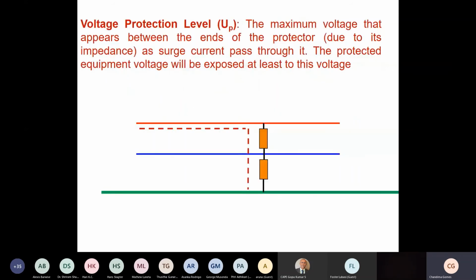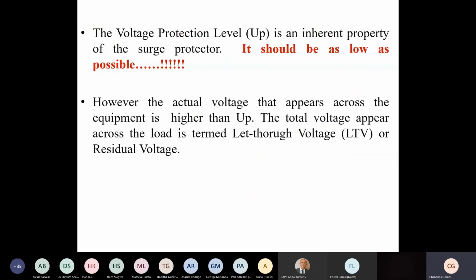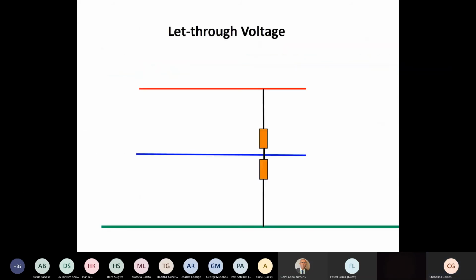So as you are now quite familiar, this is the maximum voltage that the SPDs alone will give out. But in reality, the voltage which is seen by the load is greater than the UP value because of the voltage that is generated along the connecting wires. So altogether, the voltage across the wires plus the UP is called the LTV or let-through voltage. And so let me quickly show you what this means.